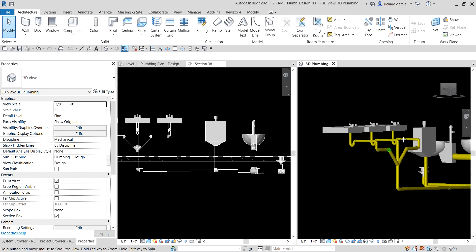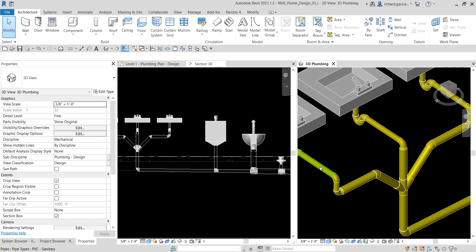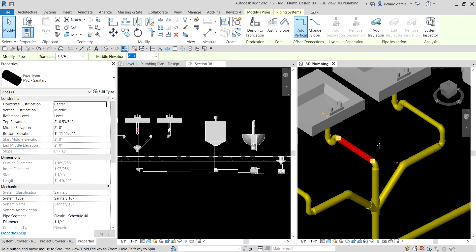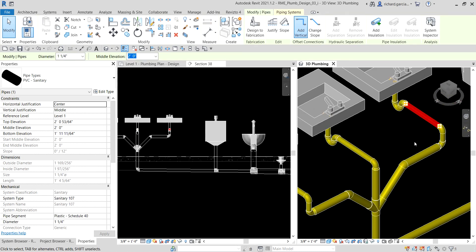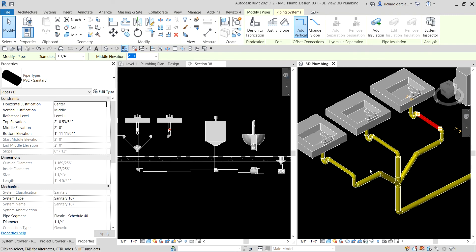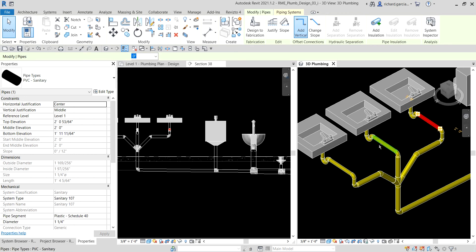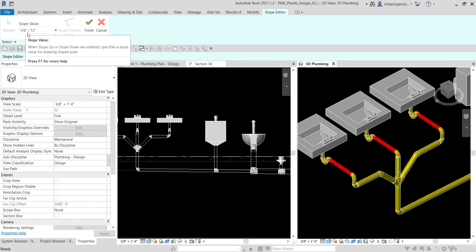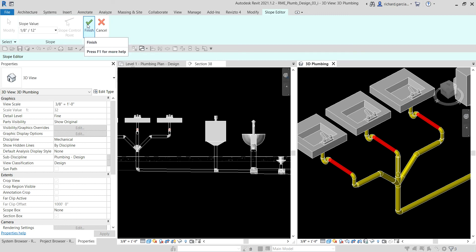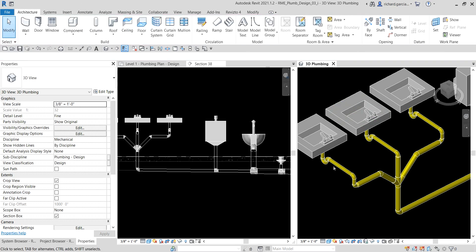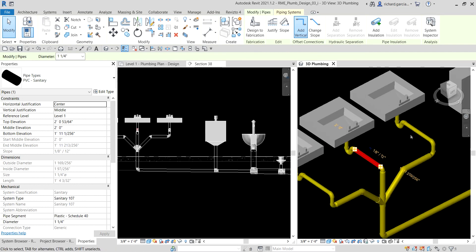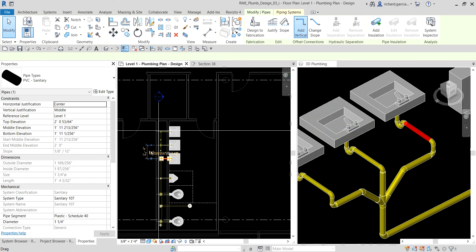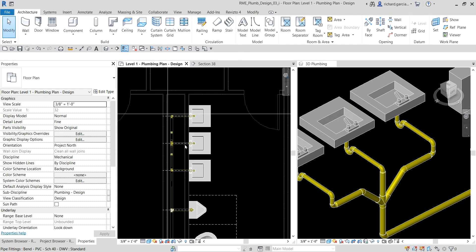I notice the horizontal pipe segments connected to the P-trap have no slope — they're straight, which is incorrect. I hold Ctrl to select all three horizontal pipes and then go to Slope, set it to 1/8 inch per 12 inches, and click Finish to apply the slope. The pipes now have the correct gradient.